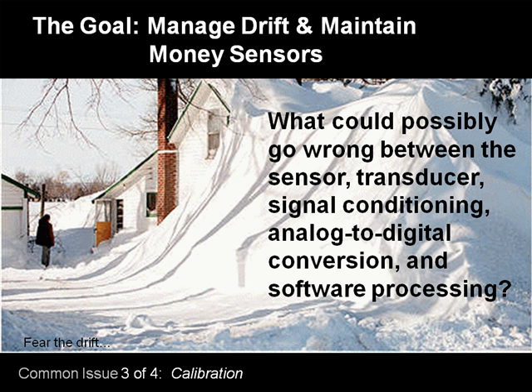Then the duct is thrown into the job box, set up on top of the duct, knocked down on the floor half a dozen times, then pulled out, stuck into the duct, and the wires put on it. It's ready to go. And we find when we're commissioning that I find temperature sensors 4 or 5 degrees off. You end up having to put an offset in there to get it back, because what you don't want to do in a high-performance building is operate above or below lines that you've set in your design. That's just going to cost money.